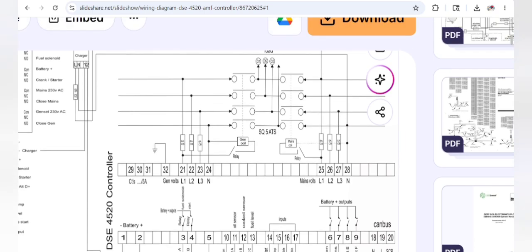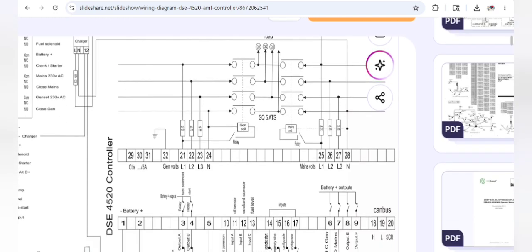You first need to set the electrical interlocking system in this controller to avoid damage or short circuit. First of all, be careful working on the ATS panel. When the main power is available, only the main contactor will be closed, and the main power will be shifted to the load. As you can see, this is our load, 3 phases and 1 neutral.